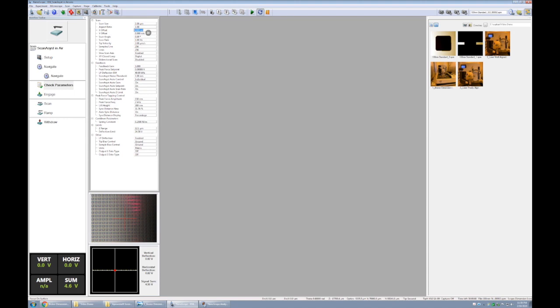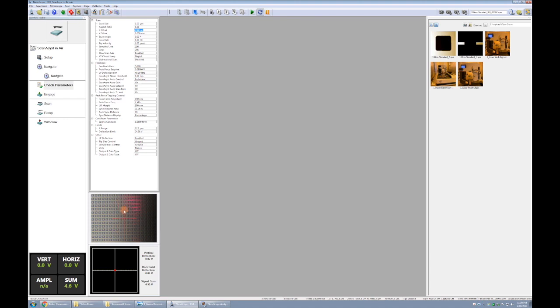The x and y offset are just a way for us to move the scanner once it's landed on the sample. So if we landed here, we would be able to move the scanner over in the x direction by a specified amount. We have 90 total microns in x and y that we can move the scanner with the piezo control. When we land, we can technically move plus or minus 45 microns in any direction.